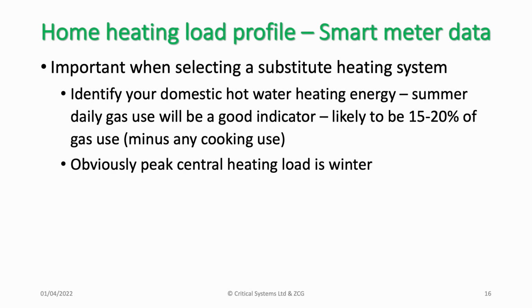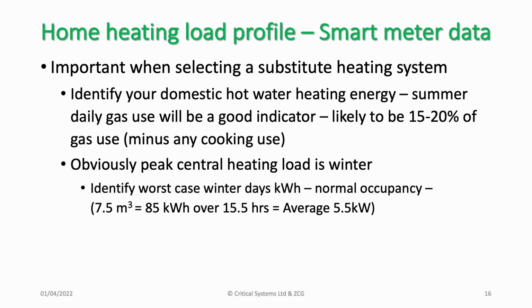Now, obviously, peak central heating load is in the winter. So identify your worst case winter days, kilowatt hours consumed, normal occupancy. So we might find over a particular day 7.5 cubic meters of gas is consumed, and this would represent, if you convert to kilowatt hours, 85 kilowatt hours, and if that was burnt over 15.5 hours during this winter day, and it turns off at night, the average consumption is 5.5 kilowatts as an energy rate.